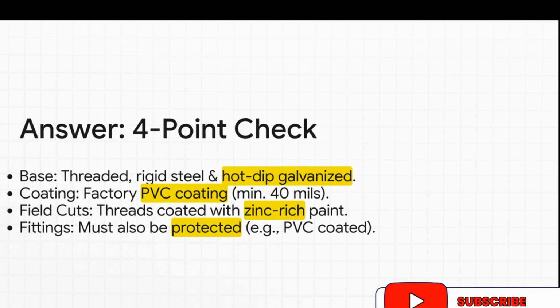You break it down into this 4-point check. You say, first, the conduit itself has to be threaded, rigid steel that's been hot-dip galvanized. Second, it needs a factory-applied PVC coating, at least 40 mils thick. Third, if we cut any new threads on site, we have to coat them with zinc-rich paint. And fourth, all the fittings need the same level of protection. See, clean, structured, and shows you know it inside and out.